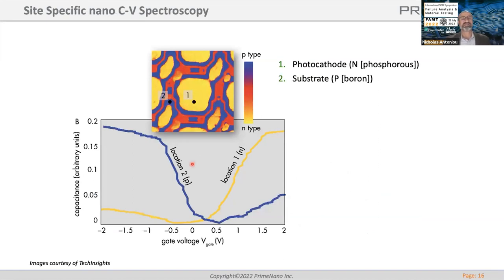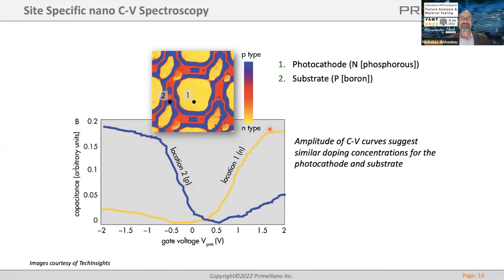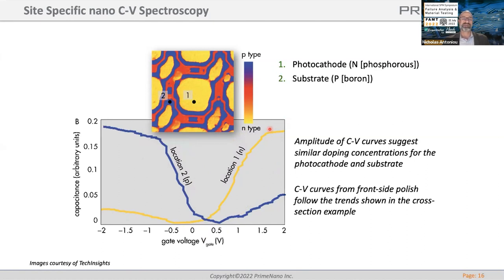Here's an image sensor that has been exposed, showing different dopant types via dCdV imaging. The phase of the dCdV tells us the polarity — red being n-type and blue being p-type. We can place the probe at a single position and do CV there. Location one shows the CV curve for that particular spot, and location two shows the p-type CV curve. That is the photocathode area of the CV curves.